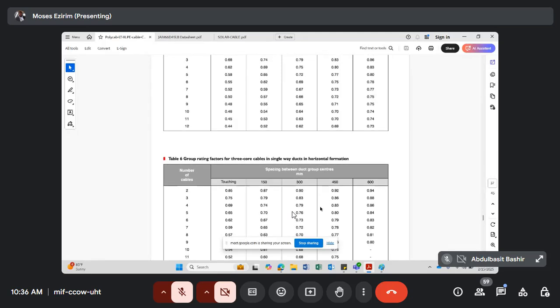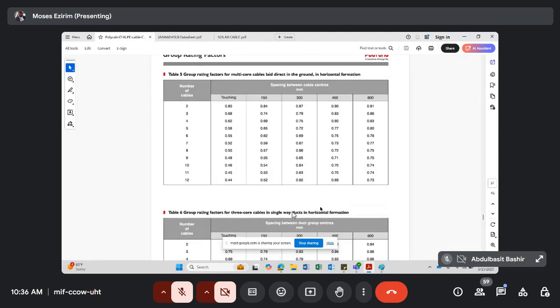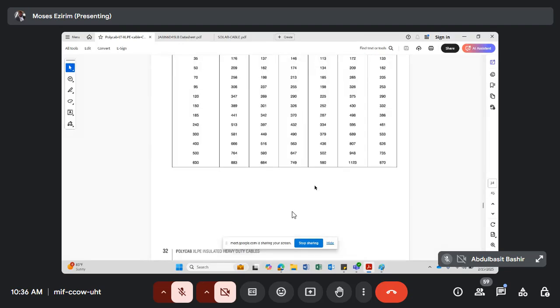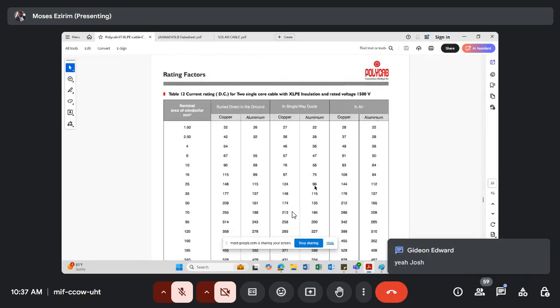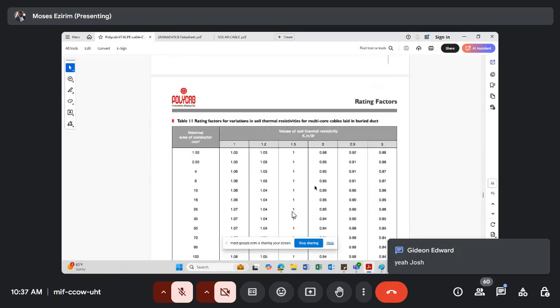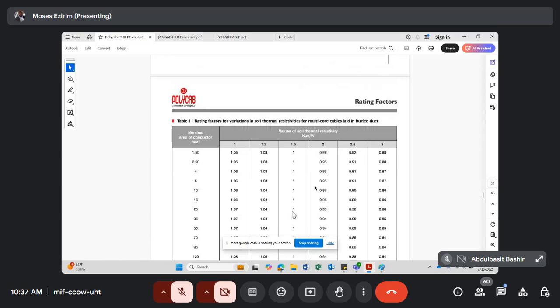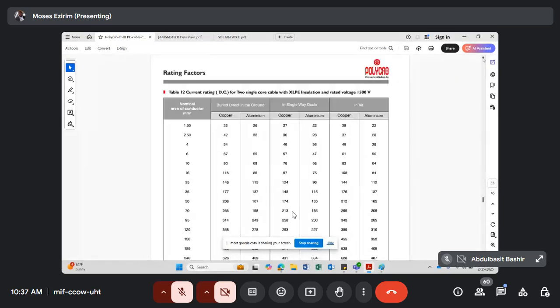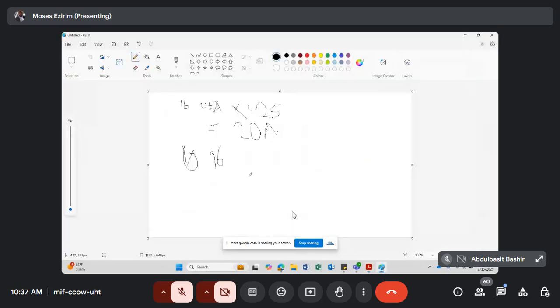Even if it is flying in the air, we are going to pass it through a duct. This might possibly delay us, so I wouldn't want this to delay us, but when you have the catalog you are going to see it. Let's just assume we are passing the cables through the ducts, and the derating factor through the duct is let's say 0.83.